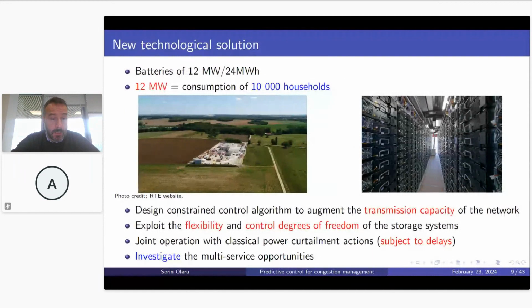So what RTE has done is construct, at very sensitive nodes, a supplementary level of control: a storage unit. There are 3 currently installed in France, with a plan for 15 more. These are very large storage units with batteries of 12 megawatts and 24 megawatt-hours—to put that in practical terms, that corresponds to the consumption of 10,000 households.